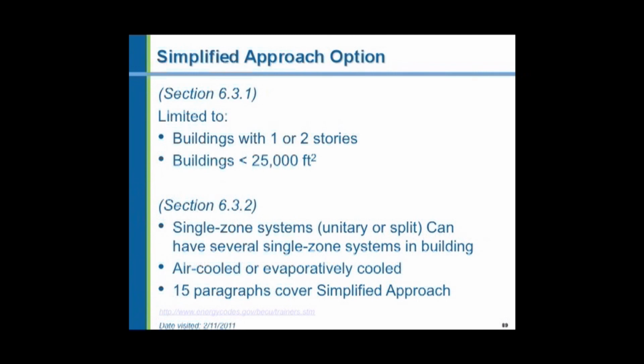Then if we have a small building, we can use a simplified approach, which is allowed only for HVAC. Or then we can go to the prescriptive path or the energy cost budget method. The simplified approach is available for the majority, I would say, of new commercial buildings. The majority of new commercial buildings are like strip malls, doctors' offices, small retail spaces. And it's limited to 2 stories or less and 25,000 square feet or less. If your building falls in this category, you need to comply with only the requirements of 15 paragraphs in the code, and you're done. You're home free. That's called the simplified approach.